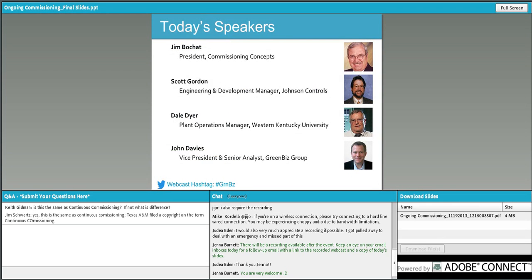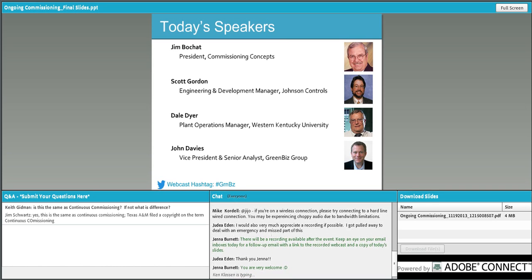All right. Thanks, Scott. Well, I've got a couple of questions that have come in that maybe we should address right up front. So one question is, what is typically required in order to gain access into a building's network so this FDD and ongoing commissioning can be performed remotely? Right. That's a great question, very important question. Actually, every building is different. There's a readiness that has to occur depending on if it's a BACnet-enabled building. If it's not a BACnet-enabled building, then there would have to be some type of gateway installed in the control system so we have access and bring the raw data up into the cloud so these high-level analytics could be done. So it's really contingent on the type of system that's in a building and how open it is or if it's proprietary.